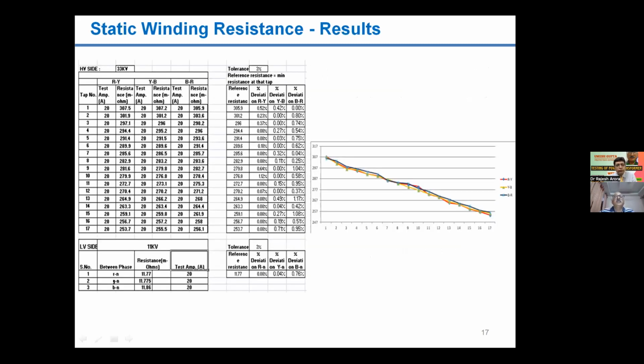This table is basically test results performed on a healthy transformer. You may see in the graph that the variation of the resistance is quite smooth. Mostly overlapping of the resistance is taking place. The x-axis is nothing but the tap positions 1 to 17, and the y-axis is the resistance itself in milliohms.